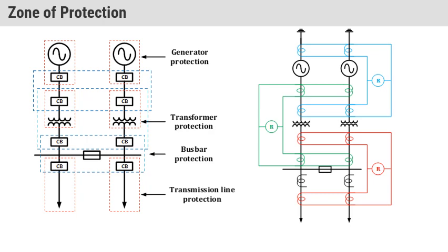Okay, and in a unit protection system we have a differential type of protection. So in differential protection, if we want to protect a transformer or generator, what we do is add a CT here and another CT here. Then we observe if any current changes between the incoming and outgoing portion, it indicates that there is something wrong in the generator.